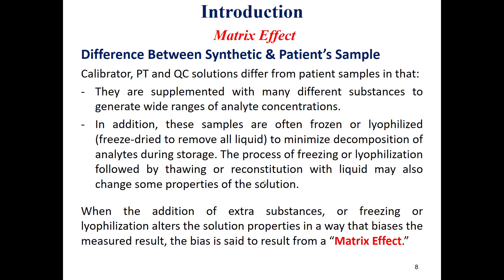This results in a difference between a natural sample (a patient sample) and an artificial or synthetic sample such as a calibrator, quality control, or proficiency testing. The addition of extra substances or freezing or lyophilization alters the solution properties in a way that biases the measured result. This bias is said to result from a matrix effect, which we should consider during the calibration process or its verification by quality control.